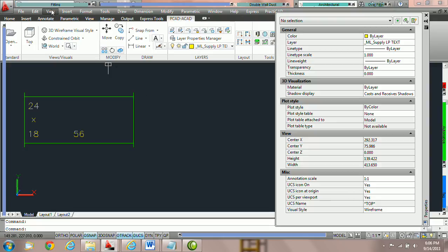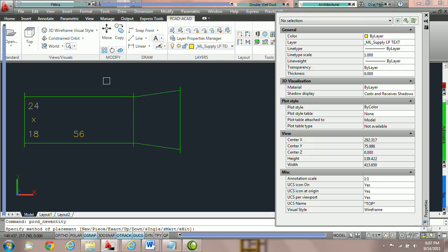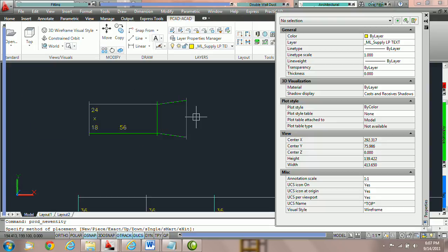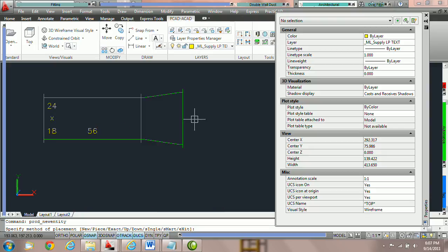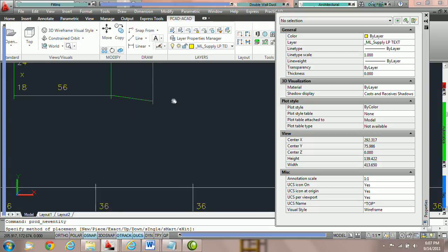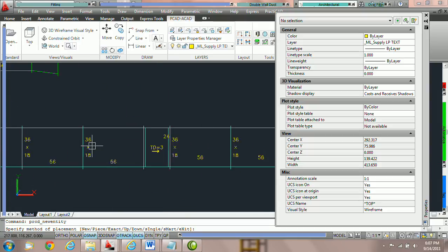And now what we're going to do is grab the same transition out of our fitting bin. And now we're on continue. You can see that it has changed the width in and depth in to match what we're attaching to, but it has not adjusted the width out and depth out. So it serves two functions: making sure the width out and depth out match width in and depth in on continue, and making sure that the change will carry up or through the nearest transition. That'll conclude the tutorial on change duct to transition.